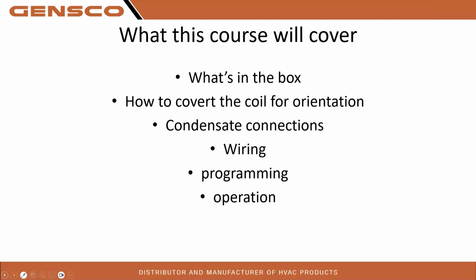So what this course is going to cover is we're going to go over what comes in the box, so all the parts and goodies that come in it. How to convert the coil for your orientation, whether you're doing horizontal left, right, upflow, downflow. Condensate connections, how to tie in the condensates, where to put the wires on that. Wiring for your 24-volt controls. Programming your thermostats or your PAC QS445s, and equipment operation, of how we're going to test run the system using the control panel on the outside of it.